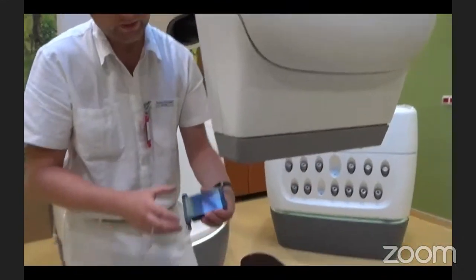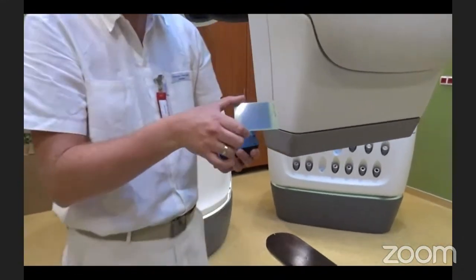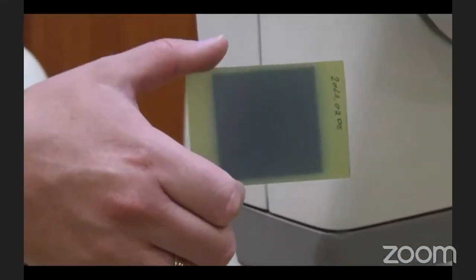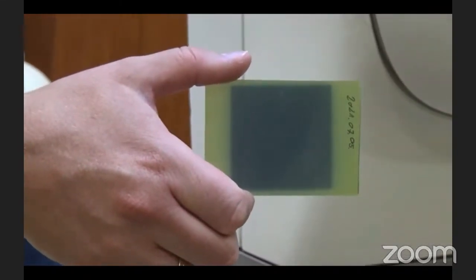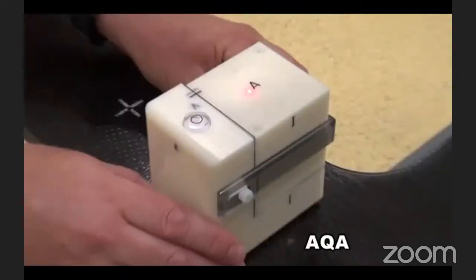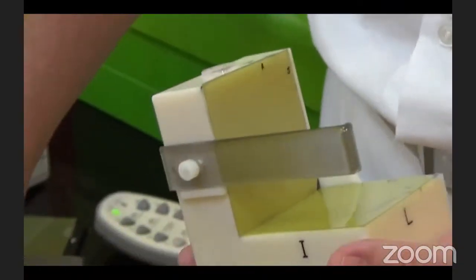After the picket fence test, we can check if the 10 different fields fit to each other or not. The third daily QA is the so-called AQA, Automated Quality Assurance. It is made by this phantom.